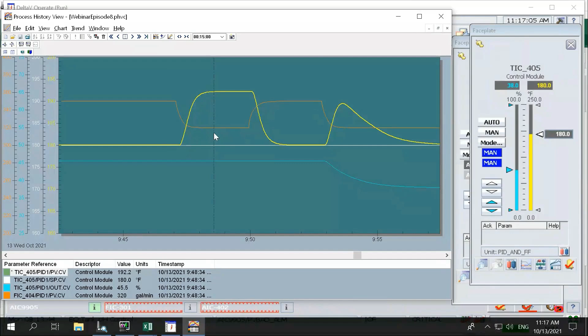I did a change in product flow while the temperature controller was in manual mode, and as I slowed down the product flow, the temperature went up. To calculate my load gain, I see how much change in temperature I get for a given flow change. That gives me my KL, and I did it twice right here.